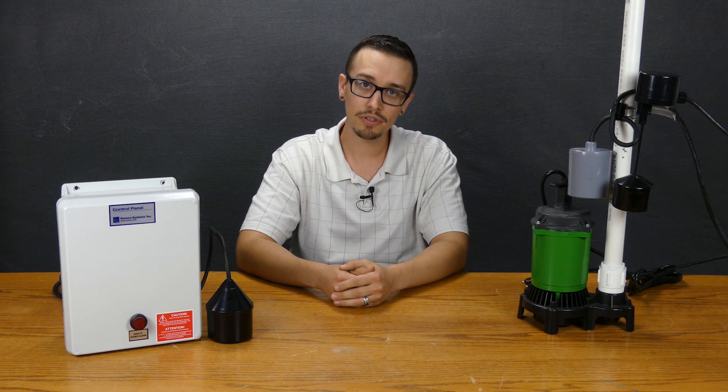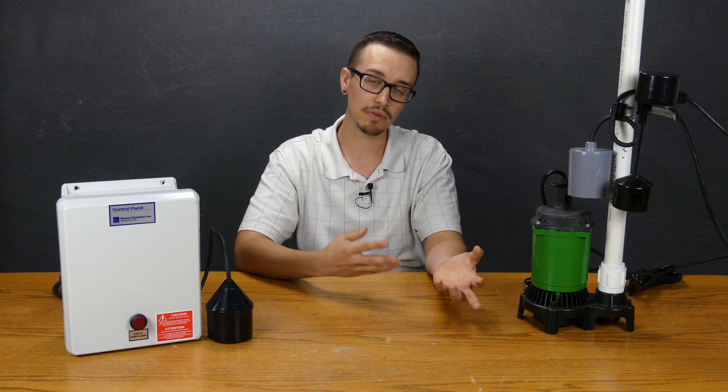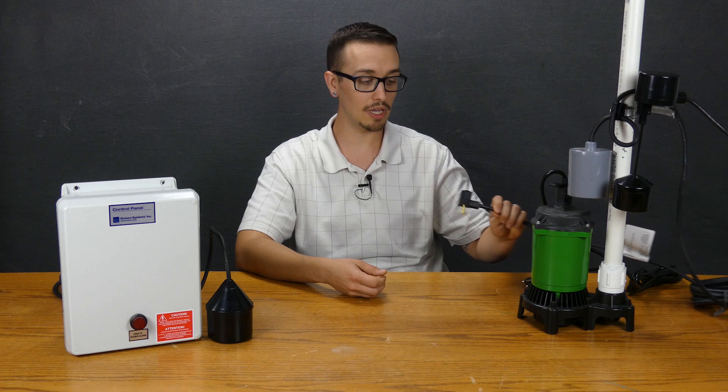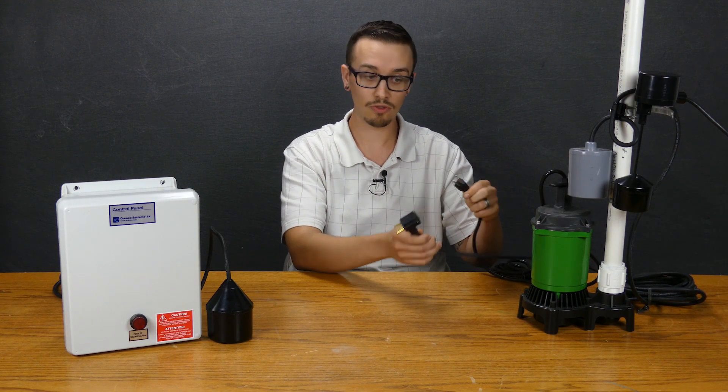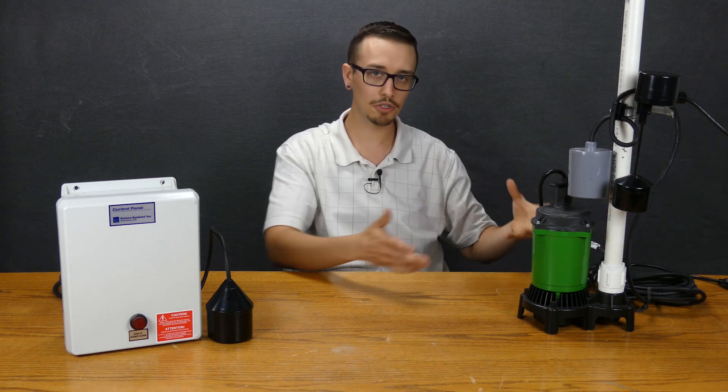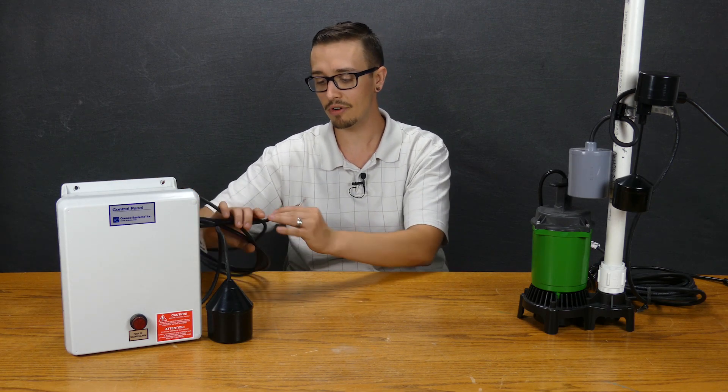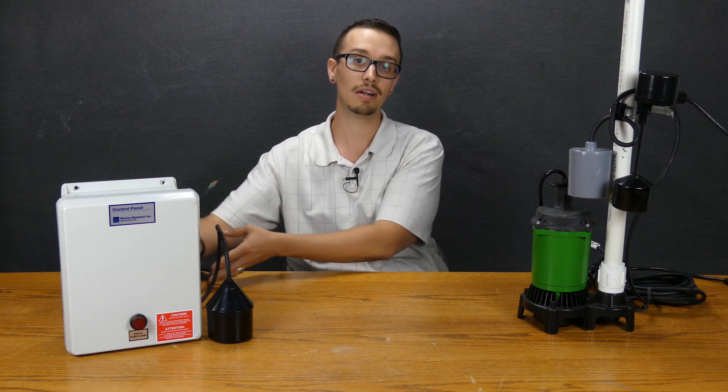One notable thing about pump switches is they are generally offered with a piggyback configuration or a no plug configuration. Of course we've all seen that piggyback before, that's the plug that then goes into a plug, this being the switch and this being the pump's power. It's real nice when you're doing some troubleshooting or anything like that. A control switch is only ever going to be offered with open wire like this because it's intended to be installed in a control panel.